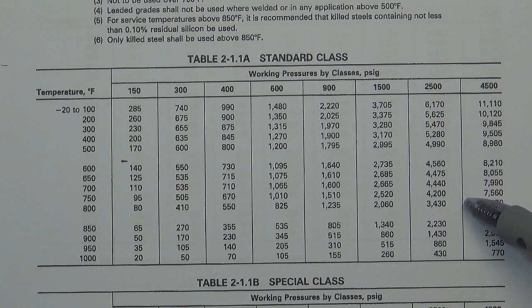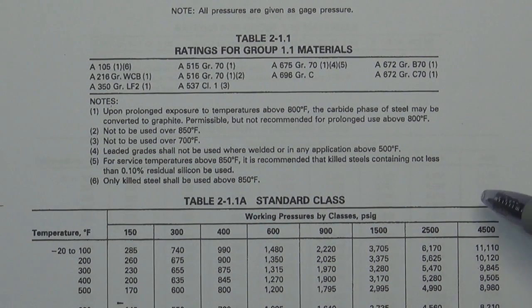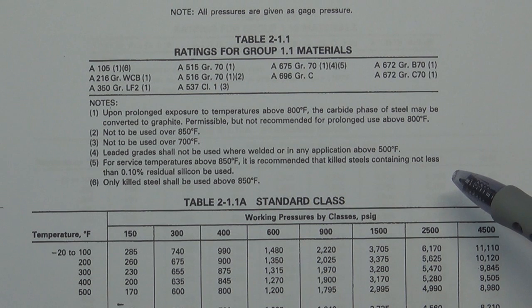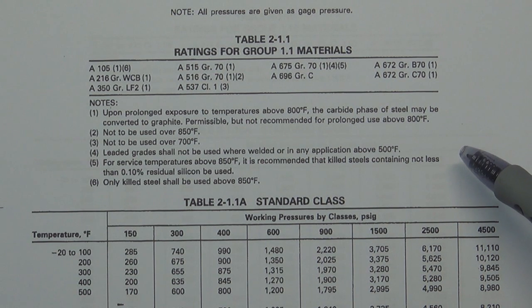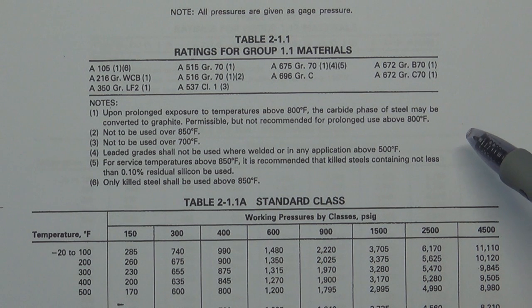When you look at this table, two things you need to be concerned about. First is the material. In the valve industry, we use a lot of different materials to make valves — for example, WCB, WC6, CF8, and CF3. Different materials have different properties, so we cannot use one pressure-temperature table for all materials. That is impossible and also not accurate.